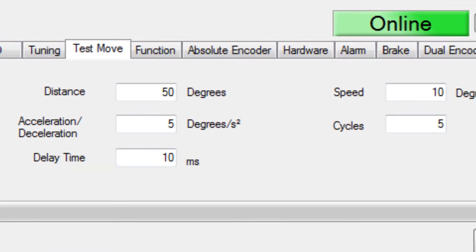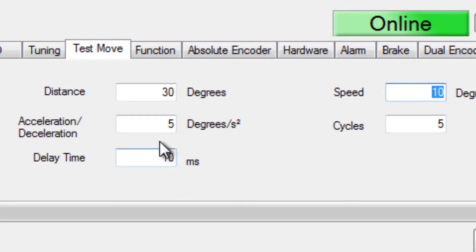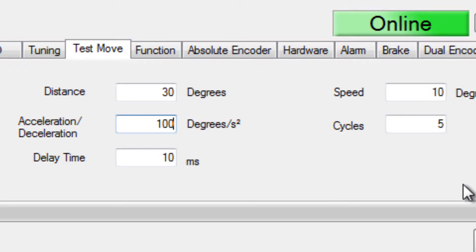Then choose a safe move distance for your machine. For this rotary axis, I'll start with 30 degrees at a safe slow speed of 10 degrees per second. Typical acceleration would be 10 times the speed, so 100 degrees per second squared, and I'll start with just one move cycle.